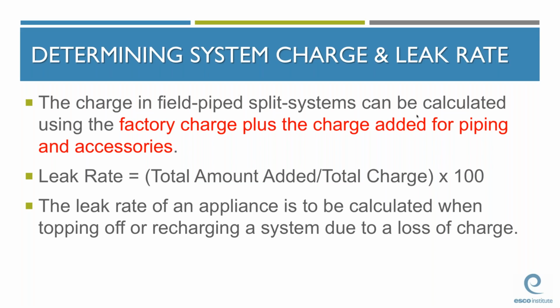The system's annual leak rate is easily calculated by dividing the total amount of refrigerant added to the system over the past 12 months by the system's total charge. With this, the leak rate will be expressed in decimal form. Multiplying this result by 100 will give the annual leak rate expressed as a percentage. So, for example, if 125 pounds of refrigerant is added to a type 2 appliance that has a total charge of 500 pounds, the annual leak rate is 0.25 or 25%.